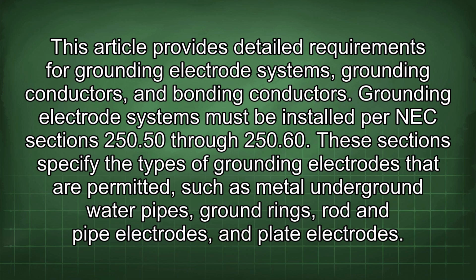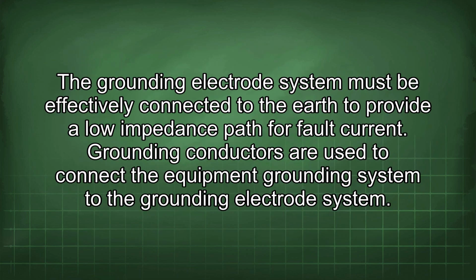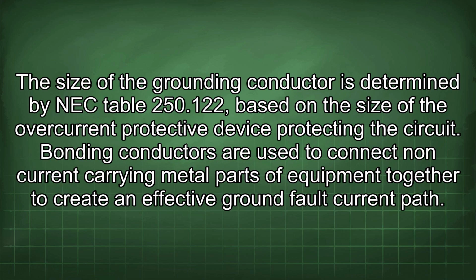These sections specify the types of grounding electrodes that are permitted, such as metal underground water pipes, ground rings, rod and pipe electrodes, and plate electrodes. The grounding electrode system must be effectively connected to the earth to provide a low impedance path for fault current. Grounding conductors are used to connect the equipment grounding system to the grounding electrode system. The size of the grounding conductor is determined by NEC Table 250.122 based on the size of the overcurrent protective device protecting the circuit.